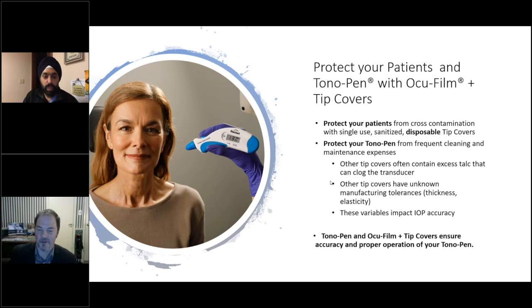Good point you made about the tip covers. I think maybe some of our audience knows that there are other brands out there, competitive brands, if you will, to the tip covers. We made our tip covers blue a number of years ago, specifically to differentiate them from the knockoff brands, because the other manufacturers have unknown manufacturing tolerances, differences in thickness and elasticity. The same sorts of things that affect the measurement of IOP because of the cornea will affect the accuracy of a Tono-Pen if those material properties are different in the cover that's going over the transducer on the tip. So those things can make an impact on the accuracy of the IOP.